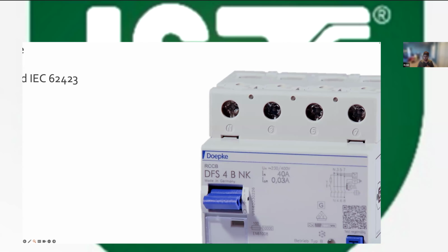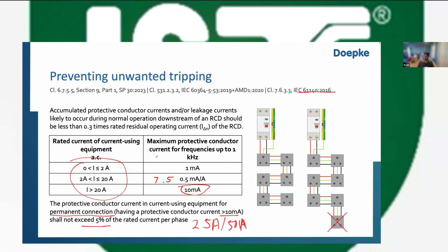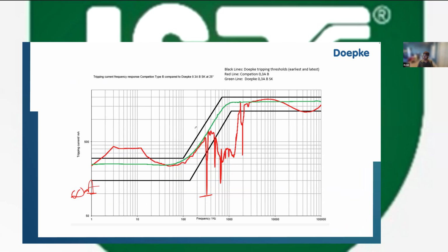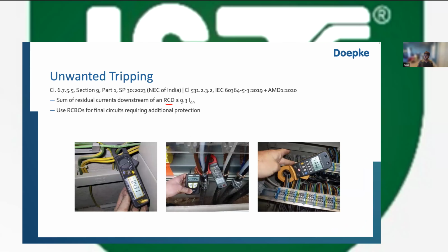In that case, what do you do? Remember what I said here. Let's say you find out you're getting 70 milliamperes. The standard requires that the rating of an RCD shall be such that the sum of all residual currents downstream shall be lesser than 0.3 times the rated residual operating current. So that means if we are getting, say, 70 milliamperes, 70 shall be lesser than or equal to 0.3 times the RCD value. Let's call that R. So 70 divided by 0.3 is 233. So R is supposed to be greater than or equal to 233.